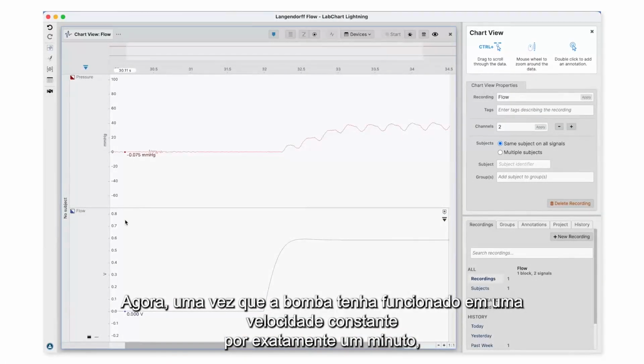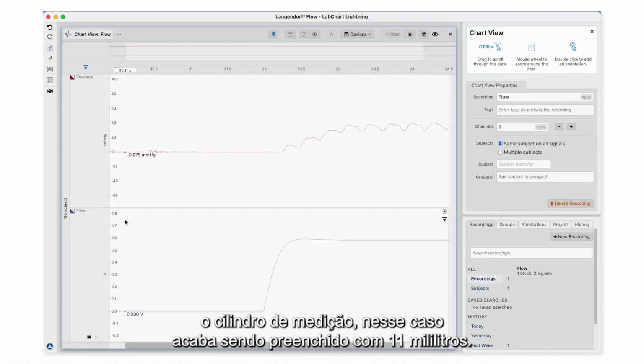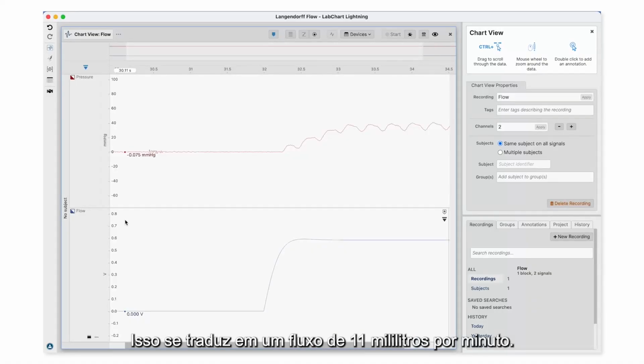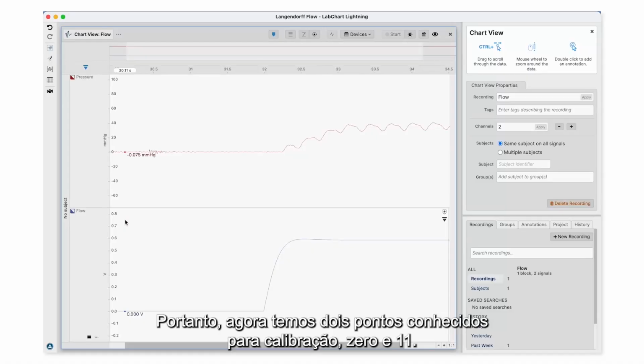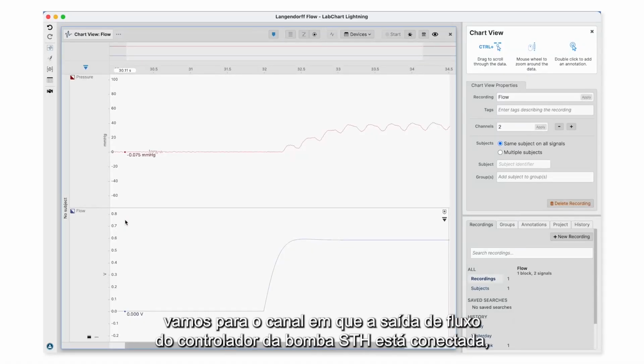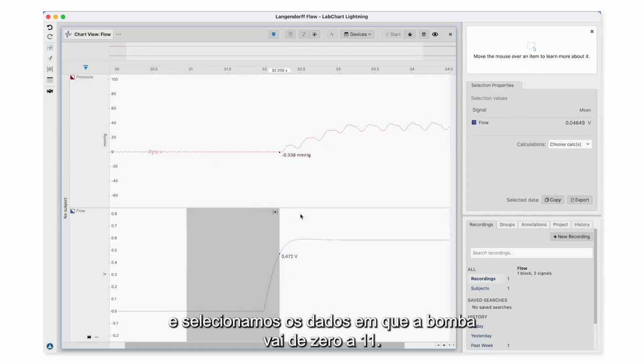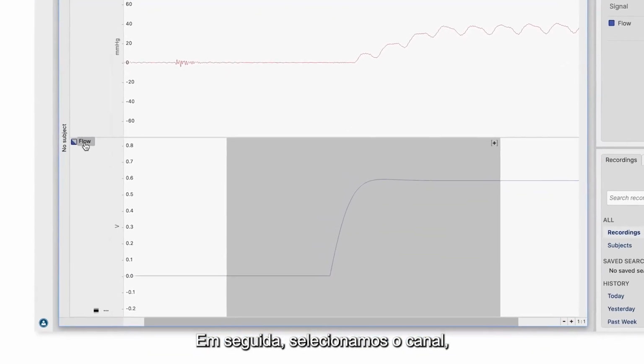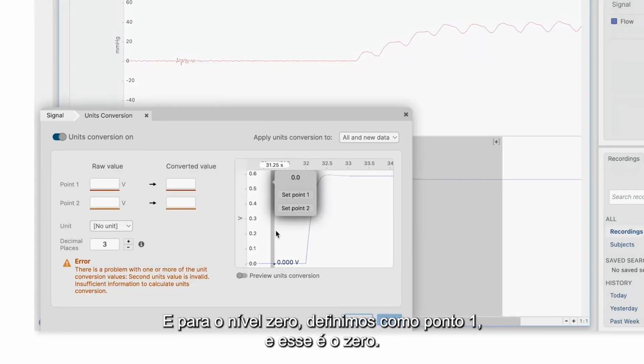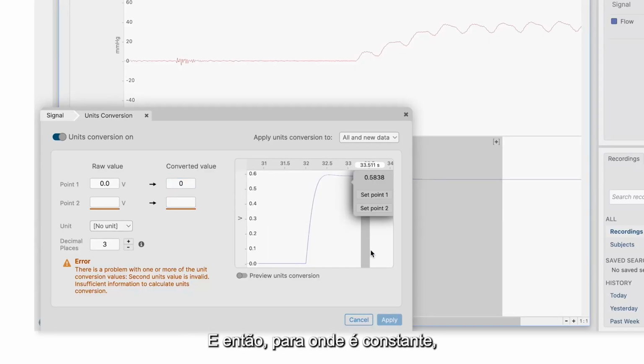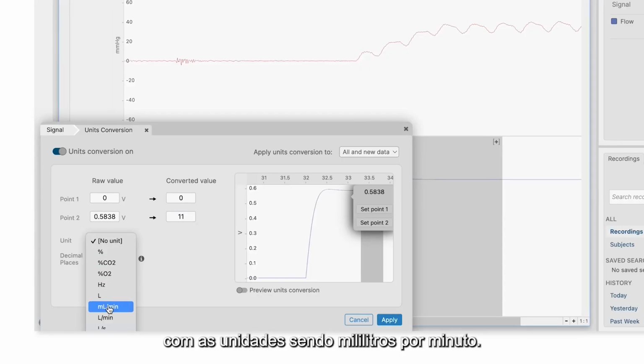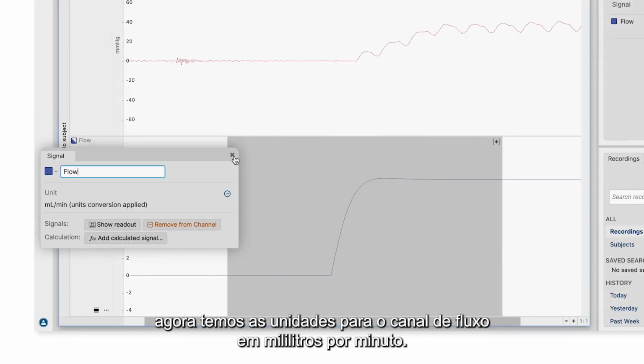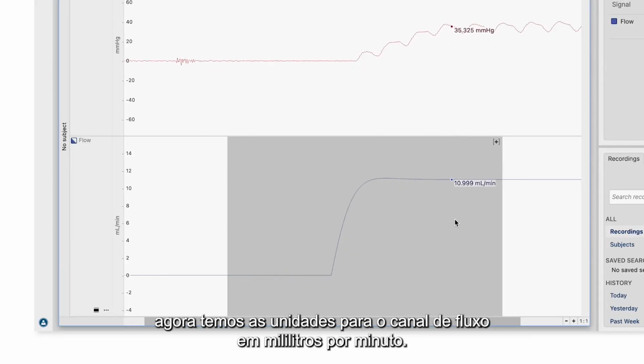Now, once the pump has run at a constant speed for exactly 1 minute, the measuring cylinder, in this case, ends up being filled to 11 milliliters. This translates to a flow of 11 milliliters per minute. So now we have two known points for calibration, 0 and 11. In LabChart Lightning, we go to the channel where the flow output of the STH pump controller is connected to, and select the data where the pump goes from 0 to 11. We then select channel, the units, and for the 0 level, we set that as point 1, that is 0, and then for where it's a constant, set that as point 2, and that will be 11, with the units being milliliters per minute. Once we apply this, we now have the units for the flow channel in milliliters per minute.